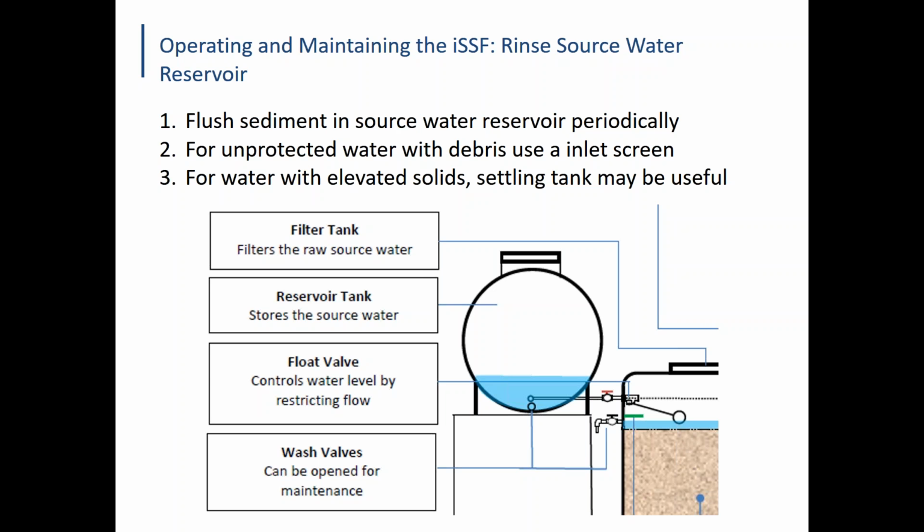But in terms of sedimentation, yeah, if you've got a high turbidity water, you'll just need to clean out this reservoir tank periodically. And that's why this isolation valve I pointed to before is there. It's not really clear here, but there can be a valve right here so that cleaning it is just a matter of opening the bottom with a large bore valve to get a nice hefty flow. And if you stick a stick in there, you can disrupt it. And these are not secured tanks either, so if they're drained, you can actually turn it on its side to clean it out as well.